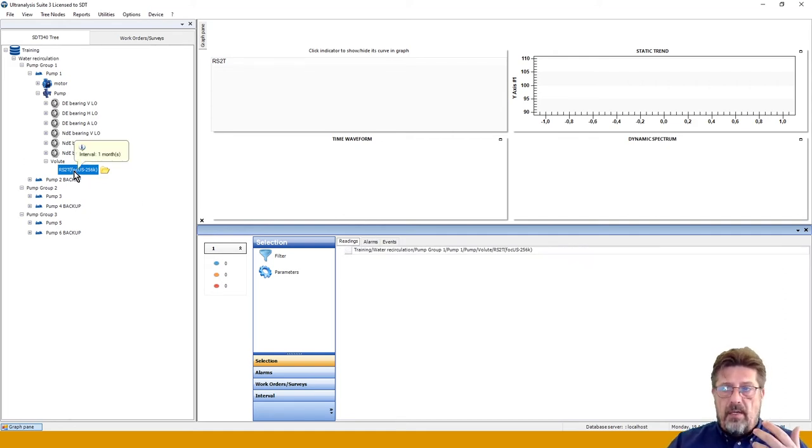But if I have 6 pumps here, and if, of course, big if, they are operating in the same range, in a similar condition, with a certain tolerance, because don't forget the baseline or the good line is never a line, it's an area. So don't expect your 6 machines to work in an absolutely identical way and give you identical numbers. That will not happen. You will not have identical reading values after 1 month, after 2 months. They will always fluctuate a little bit. So that's how I will create alarms based on real data.